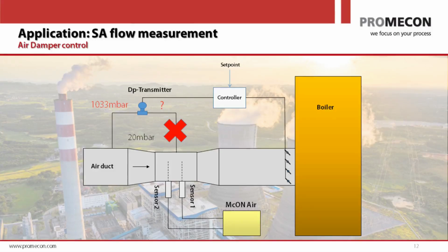The next slide shows you a typical arrangement to measure airflow into a boiler. It's a very old principle of measuring airflows. It goes back to a very smart physicist, I think it was a Swiss guy, by the name of Mr. Bernoulli, and he detected that if you have an obstacle in a large air duct and the air is accelerated by this obstacle, such as a venturi, then the airflow will be proportional to the square root of the delta pressure over this obstacle. So you have, let's say, a venturi.